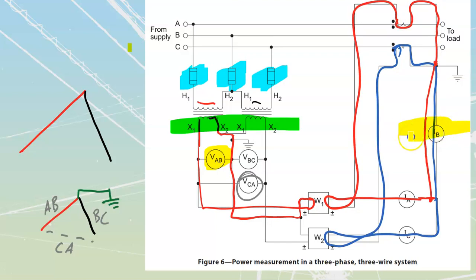This is simply doing some phasor addition. The meter doesn't know that's what it's doing, but it reads the net sum of my A current and my C current, because all the currents should balance out. In other words, if I have current coming in on A and C, I would have to have current coming out on B.